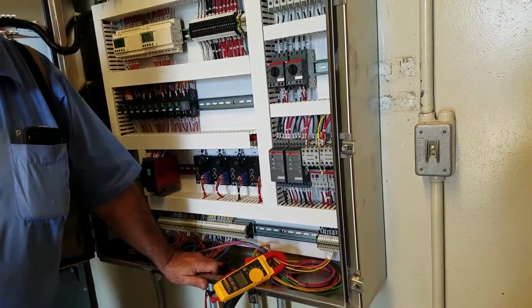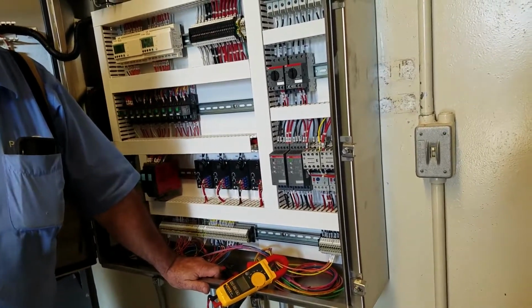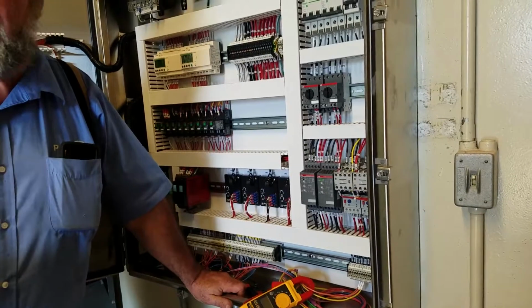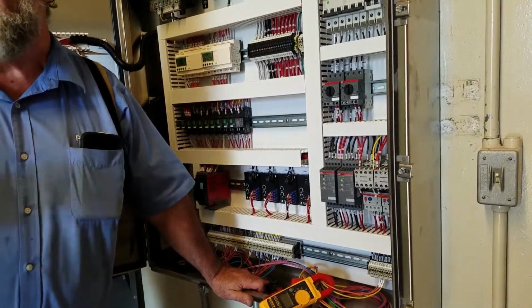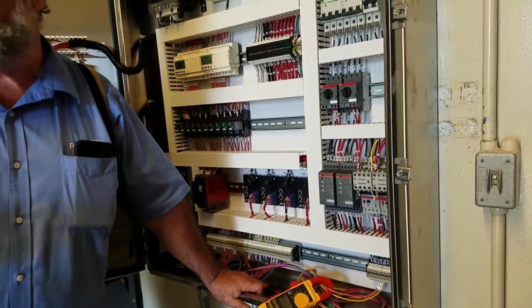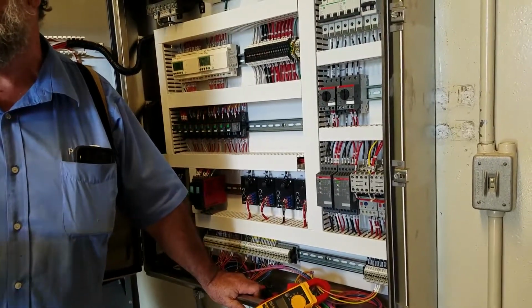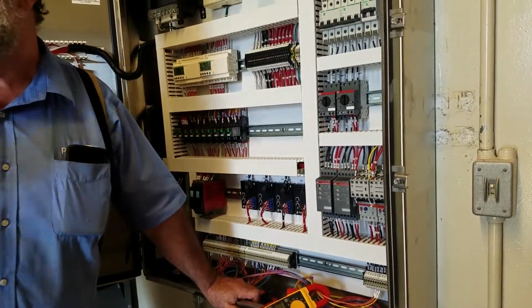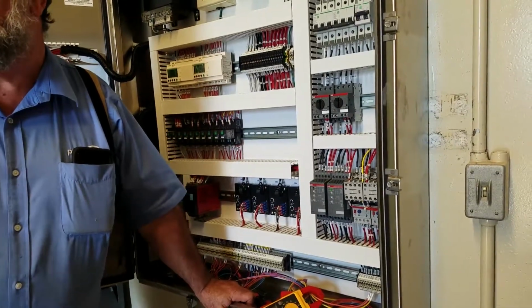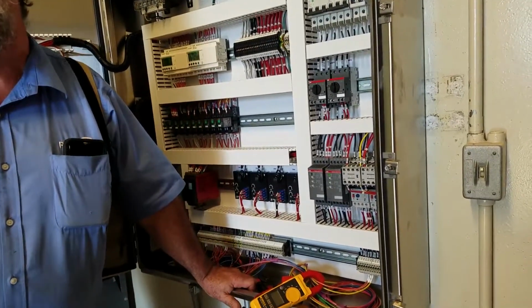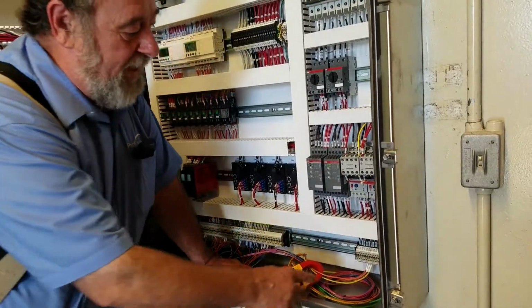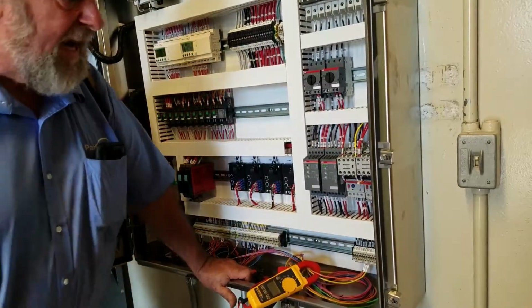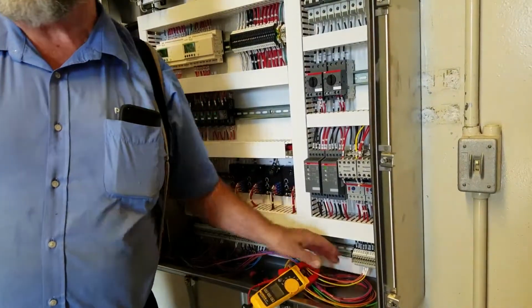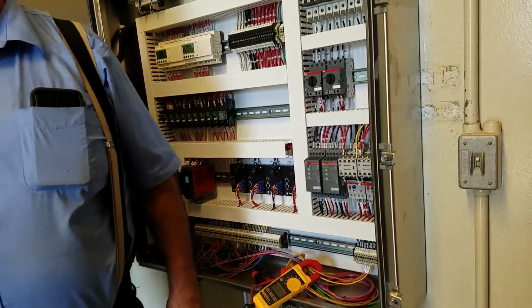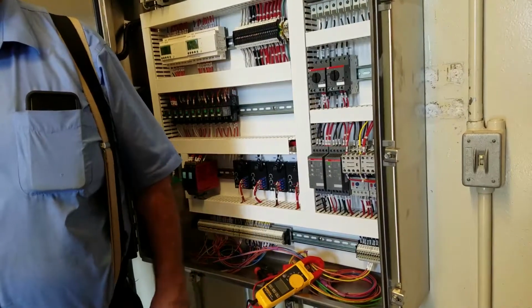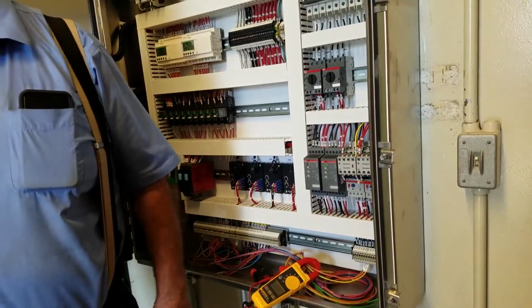Megger test it. If you've got a failure, the next thing you do is take the wires off the connection box of the motor and megger test the motor at the motor. There's other names for those flex conduits, but we don't want to say that. You got those rubber hoses, those are great, I love them. Anyway, you check it out there, and if it passes the test, it's got some problem like water in the conduits. I've had problems where we've had water in the conduits, and you tell them, well, get the water out of the conduits and seal them up so they don't get wet again.